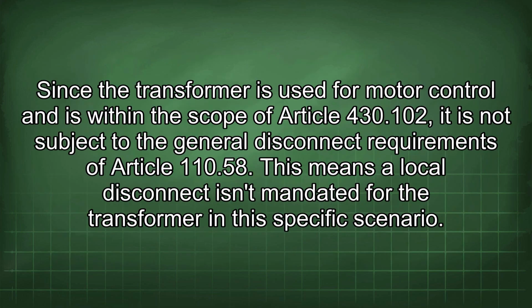Since the transformer is used for motor control and is within the scope of Article 430.102, it is not subject to the general disconnect requirements of Article 110.58. This means a local disconnect isn't mandated for the transformer in this specific scenario.